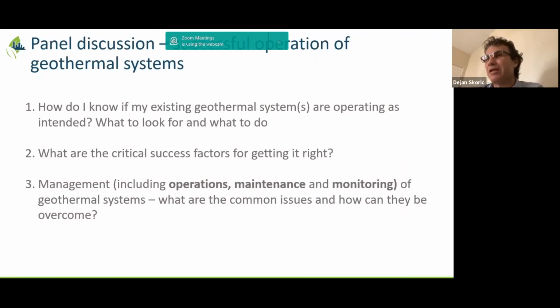If you need to get more heat into the loop, and you have a backup boiler, turn it on for a couple of days to raise the heat. Those are points critical for operators to keep the ground loop balanced. As long as it's designed properly and operators know what they're supposed to do, it's fairly simple to maintain the balanced loop. The problem happens when they have no idea what the proper temperature should be, and even if they know, they have no idea what to do about it. Then usually nothing happens until it becomes a big problem.